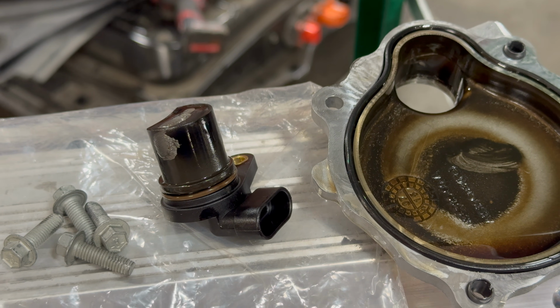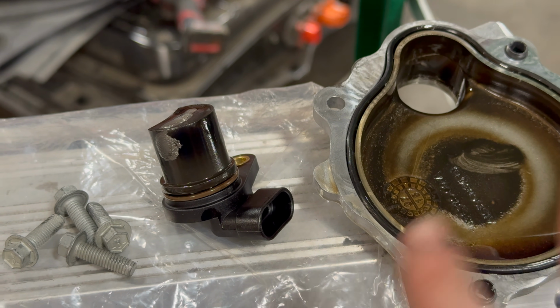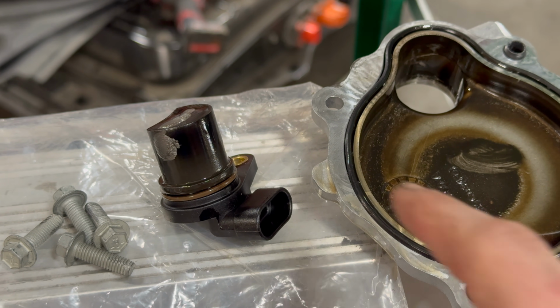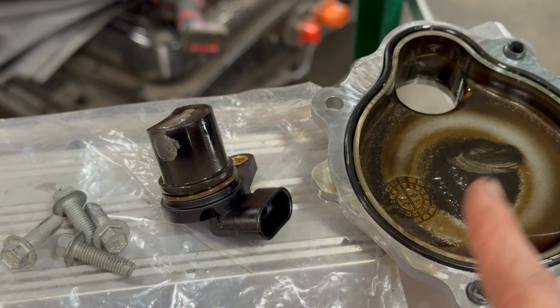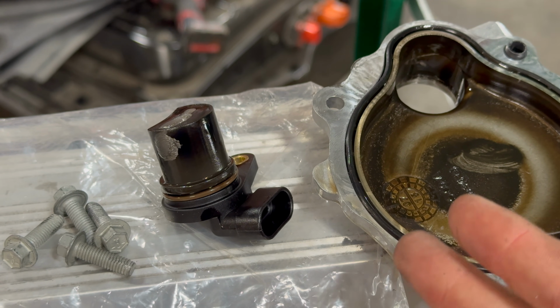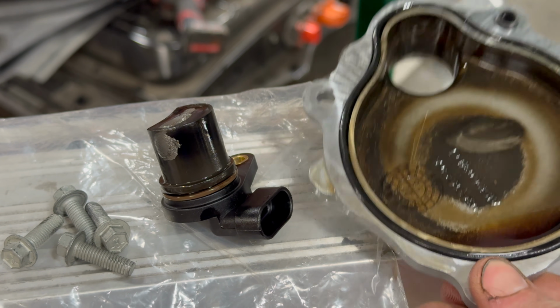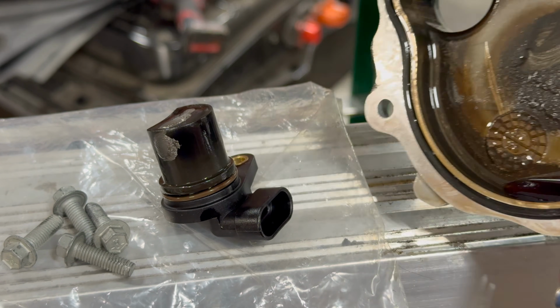Made a bit of a mistake here. This motor actually doesn't have any seal between the encoder housing and the rest of the gearbox. It's actually just open through a bearing cage, so it's perfectly normal for there to be oil in here.